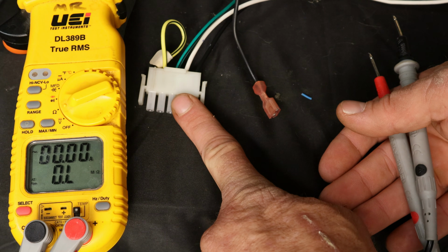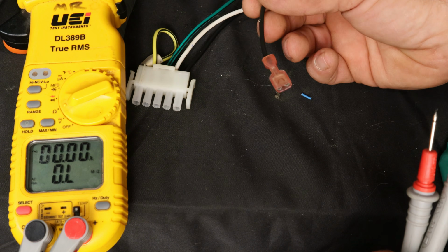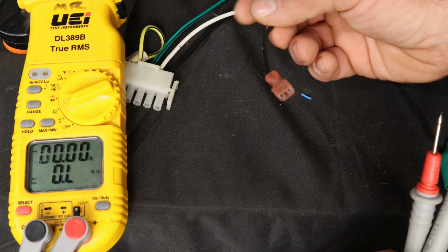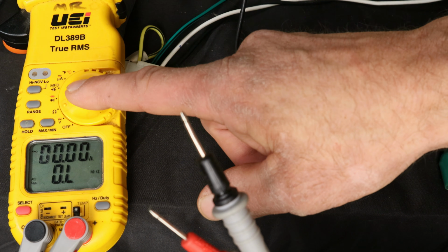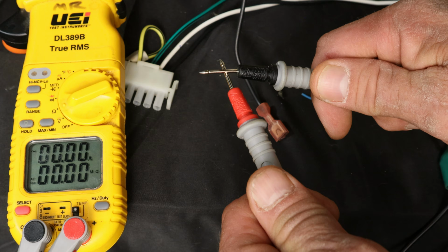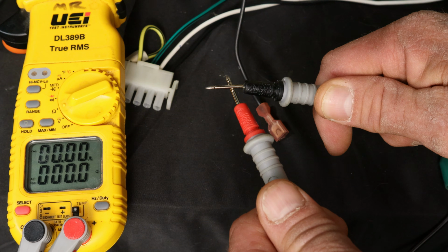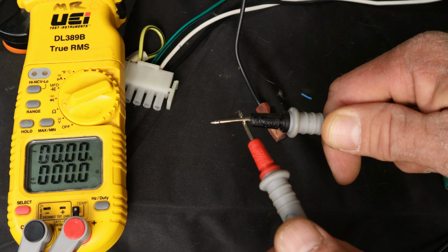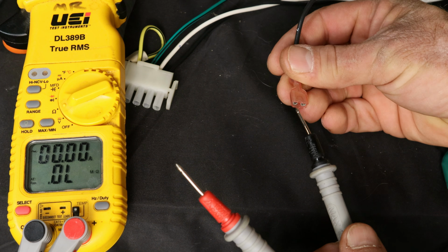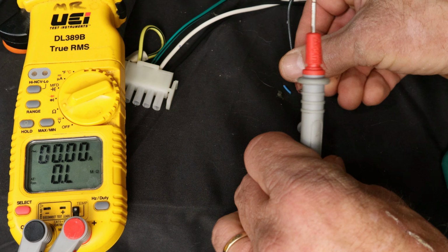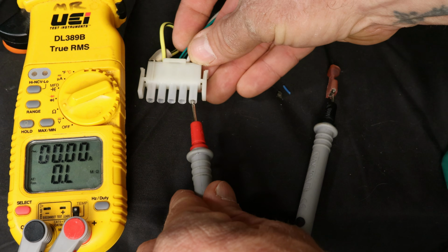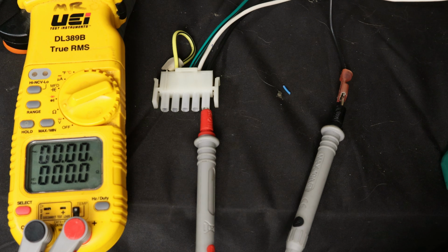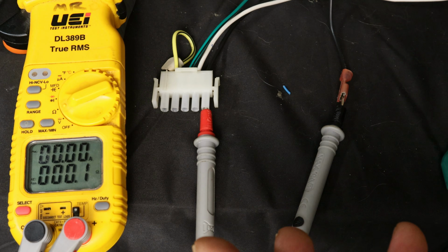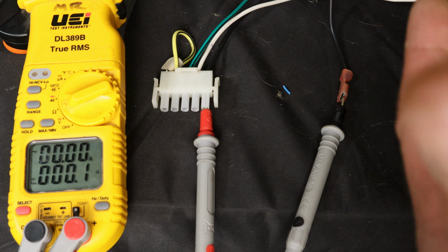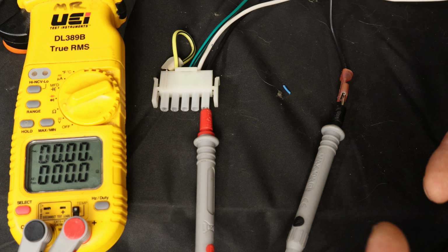So to ohm that wire out, I went ahead and shut the power off. I disconnected the Molex plug from the motor, and I took the hot wire off the control board that feeds the Molex plug, and I put my multimeter in the ohm setting. You want to test your leads. You want to make sure you're reading 0. If you're reading anything higher than 0, it's time to replace your probes. So you're seeing good there. So what I do now is put one lead on the black wire from the control board, one lead on the black wire in the Molex plug, and you should read 0 ohms if you have a good wire. If you're reading high resistance or you're reading OL, the wire's the problem. Now you can also do the same thing with the neutral.